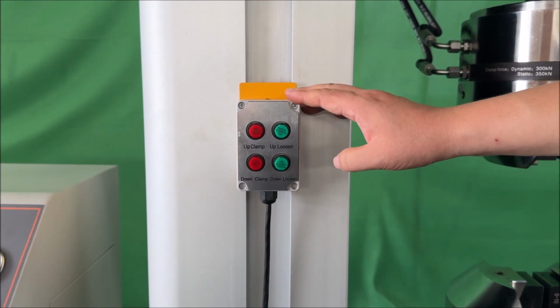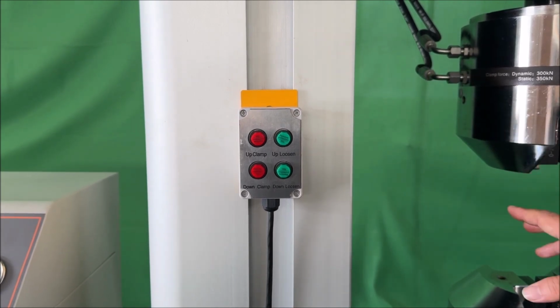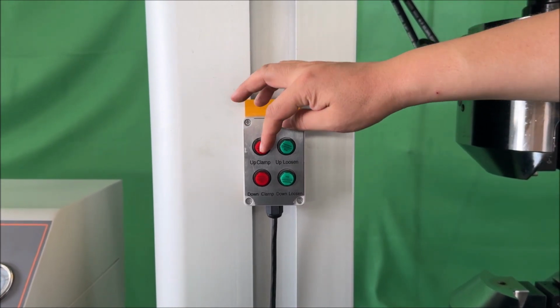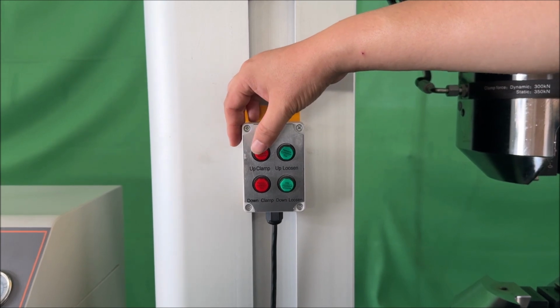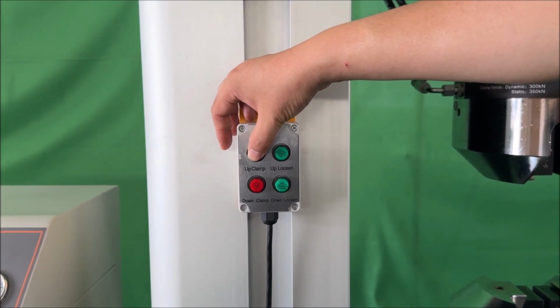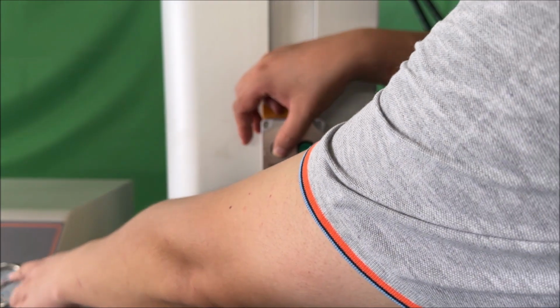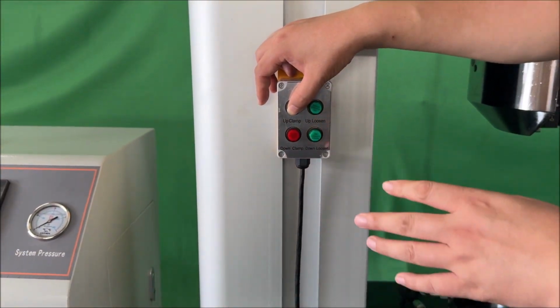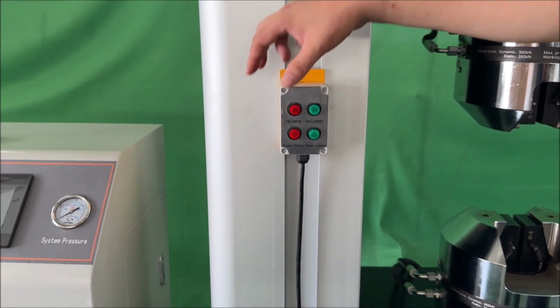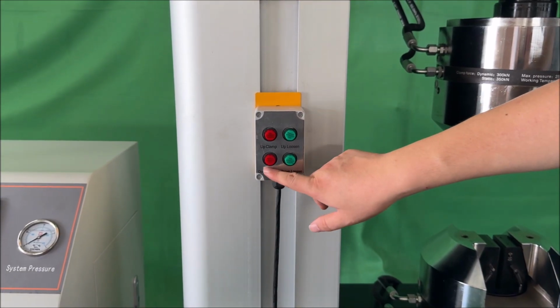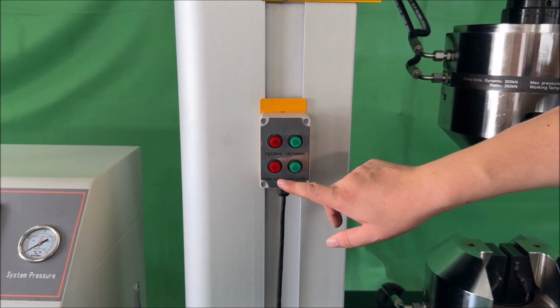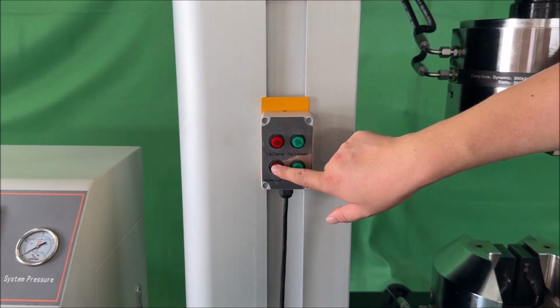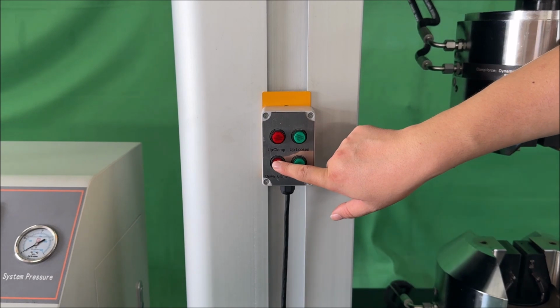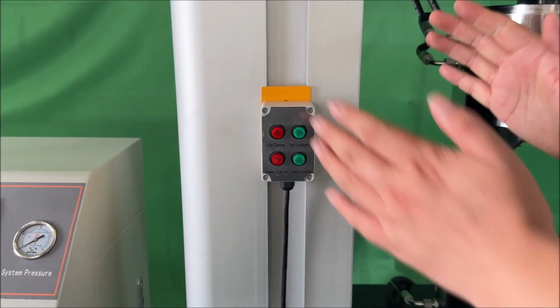When using the manual hand control box to clamp and loosen, press a button, for example, upper clamp, and monitor the system pressure. Once the pressure reaches 2 megapascals, release the button. The grips will gradually move toward the indicated target pressure. The same procedure applies to the lower operation. Hold the button until the pressure reaches 2 megapascals. Once this level is reached, you can release the button and the system will continue to attain the target clamping pressure.